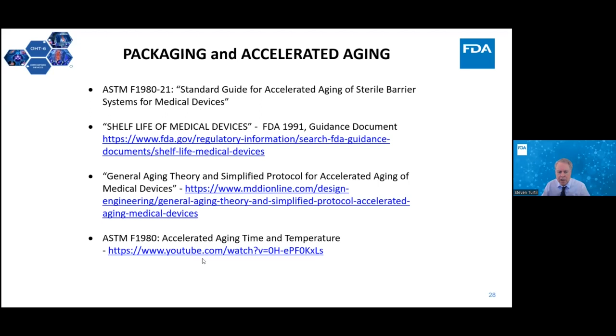Let's talk now, since we've kind of done a general introduction, more than a general introduction, I want to look at accelerated aging carefully. These are references. You feel free to reach out and take a look at it. This is the standard itself, ASTM for accelerated aging. It's ASTM F1980, but this is the year of publication. So this is the most current version, and we happen to recognize that. This is a little dated, but it's our guidance document, has a lot of good information in it. This is from an online publication. And if you go to this link, you will actually find some good information that is in the very first standard that's mentioned up there. So that's a very good introduction to the actual standard.